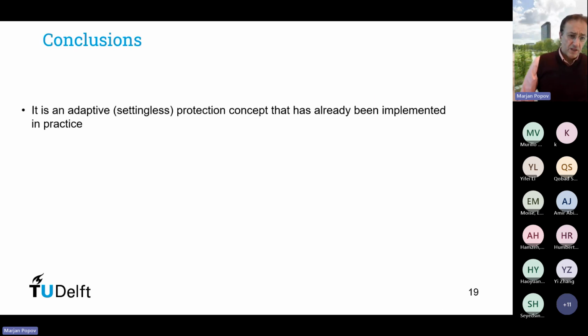The conclusion of this is that the adaptive settingless protection concept is found to be very powerful. It has already been implemented in practice. And this was a scientific project that was also supported by General Electric and the system operator in the Netherlands, TenneT. However, we could not implement this in the Netherlands because in the Netherlands we have short lines and normally this out-of-step condition practically does not exist. However, it was implemented in Iceland, where actually we have an island. And normally, when we have splitting in the power system, then it is expected that the voltage may oscillate.